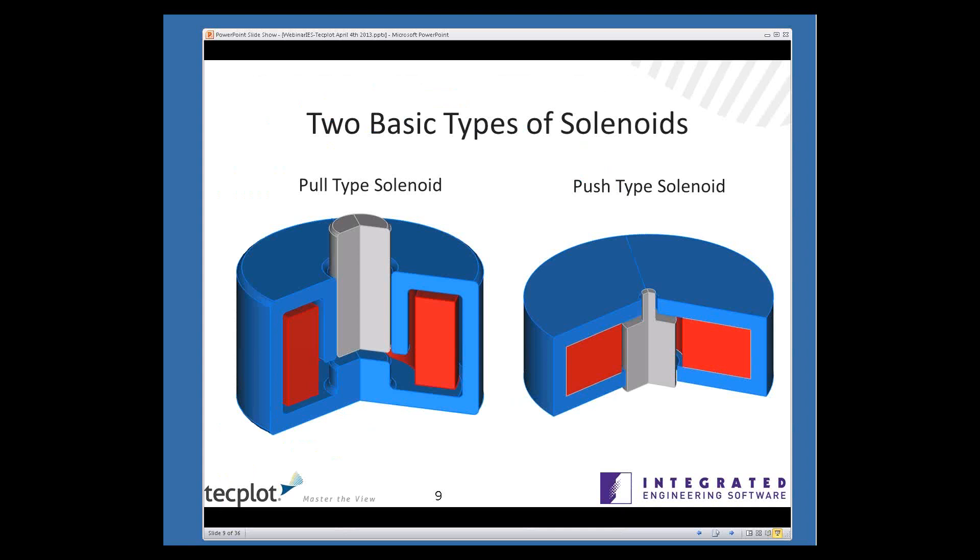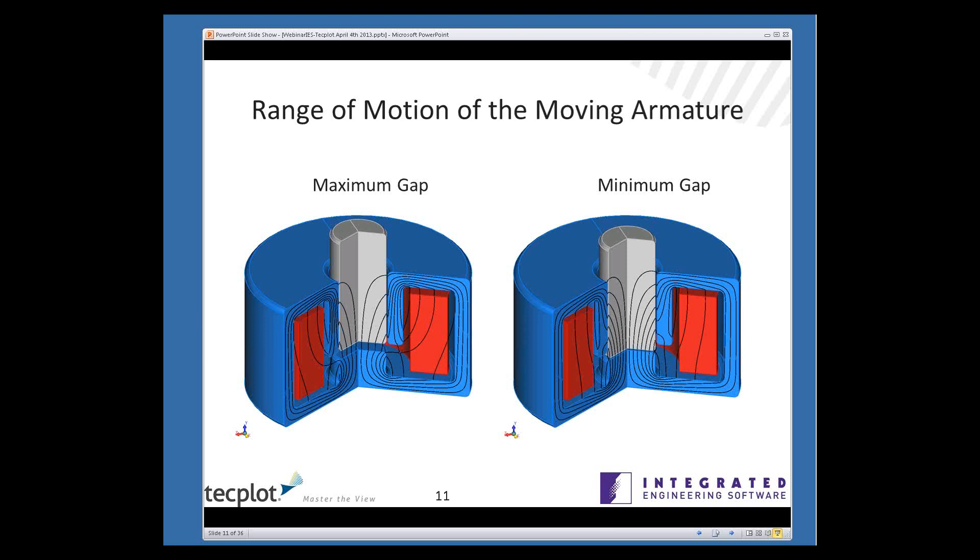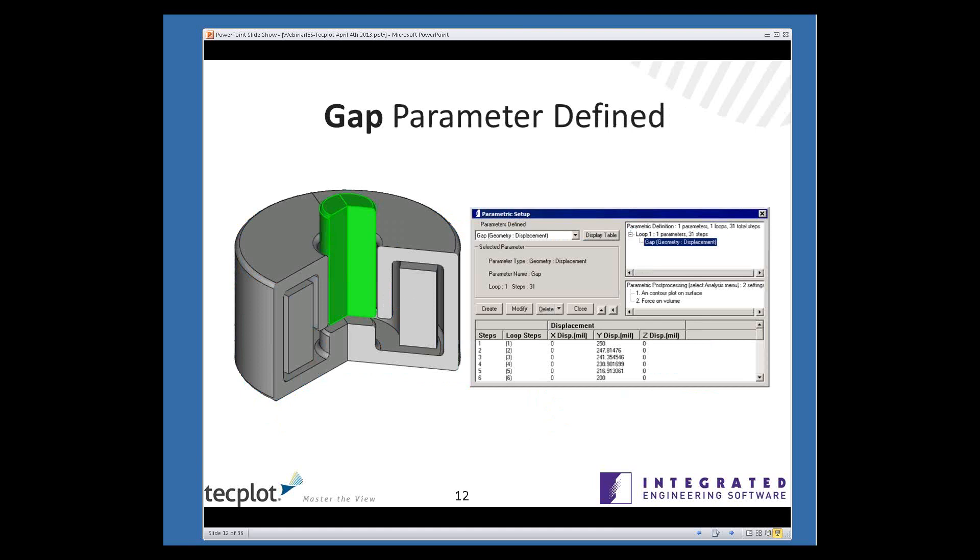Usually in any kind of a design, you're going to have to create a large number of model variations. Perhaps you have to investigate the performance of a particular prototype over its operating range, or you might want to try several different prototypes. So all of our software packages have a parametric utility, which make it very easy to create these model variations. I'm going to demonstrate the parametrics with the first type of analysis, the range of motion type parametric, and I'll do that using the pull type solenoid, and I'll move the armature from its maximum gap to its minimum gap.